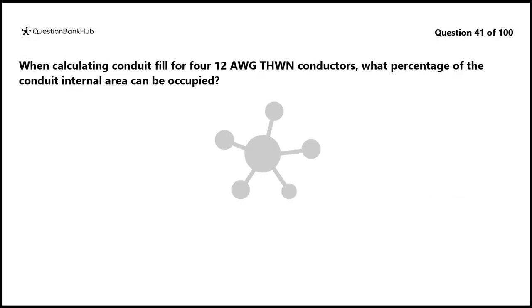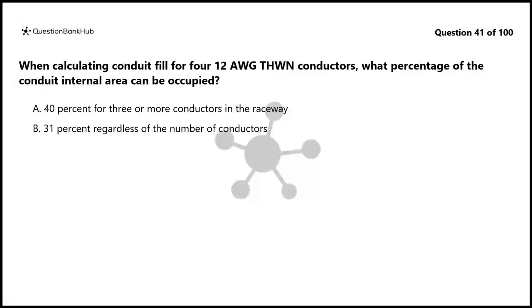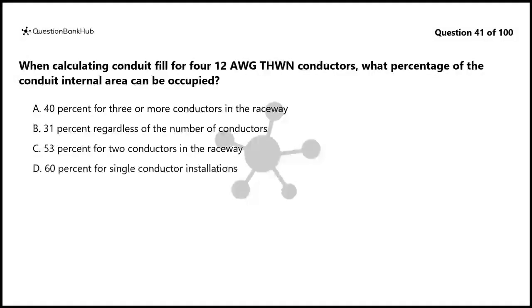Question 41. When calculating conduit fill for 4 12 AWG THWN conductors, what percentage of the conduit internal area can be occupied? A. 40% for 3 or more conductors in the raceway. B. 31% regardless of the number of conductors. C. 53% for 2 conductors in the raceway. D. 60% for single conductor installations.